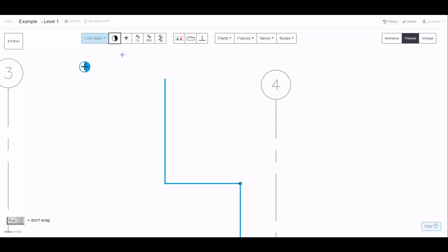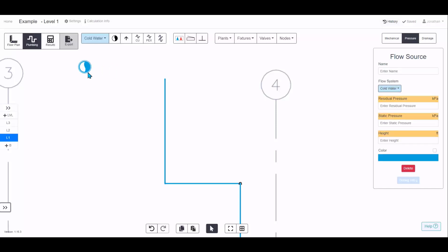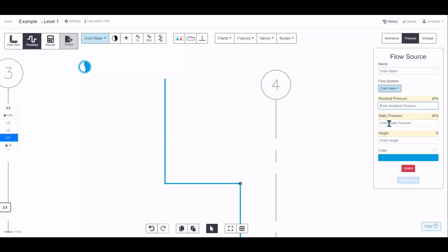Click where you want to locate it and then you can enter the name, the residual and static pressure. It's going to look at the worst-case pressure calculations using the residual and the best case with static.